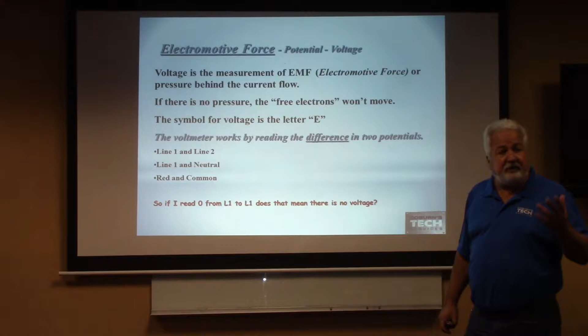Line 1 to neutral, red to common - any one of those are two different potentials. If I read 0 from L1 to L1, does it mean there's no voltage there? No, it doesn't. Just because the voltmeter says 0 does not necessarily mean there's no voltage there. Is that correct? Correct. Good.